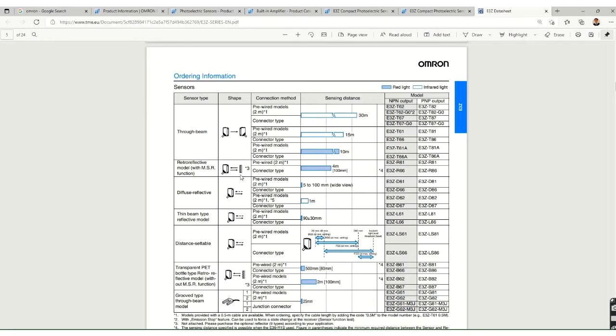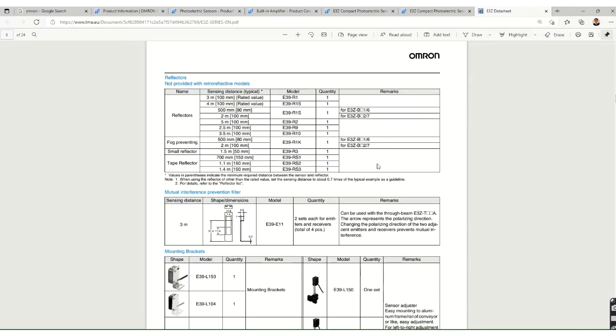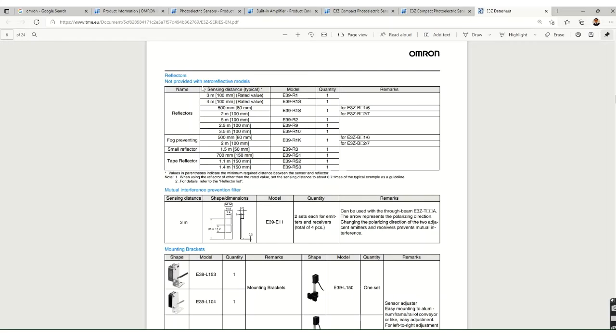For the retro reflective model, the range is up to 4 meters and 'R' in the model code indicates retro reflective. For diffuse reflective, the range is 5 to 100 mm or up to 1 meter, and 'D' indicates the diffuse type. Reflectors for the retro reflective model are not included and must be ordered separately — this is an important detail to keep in mind.